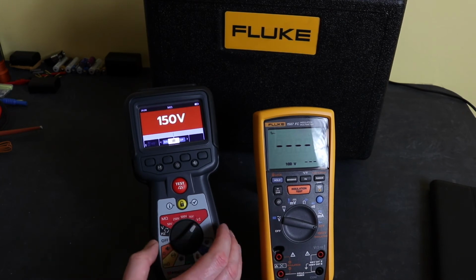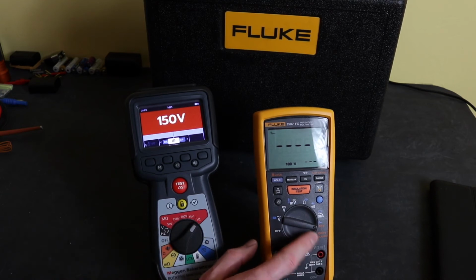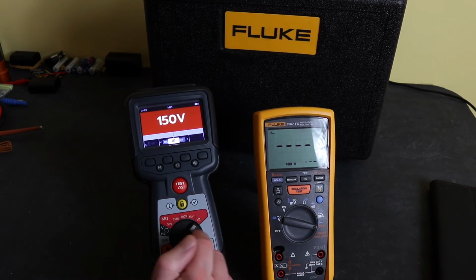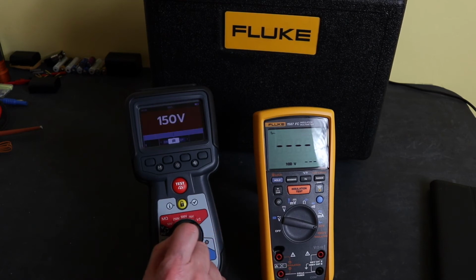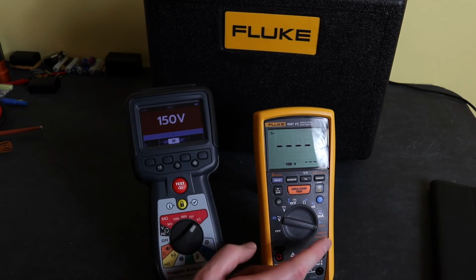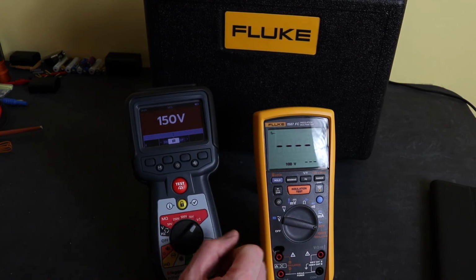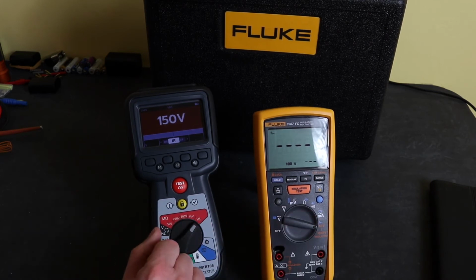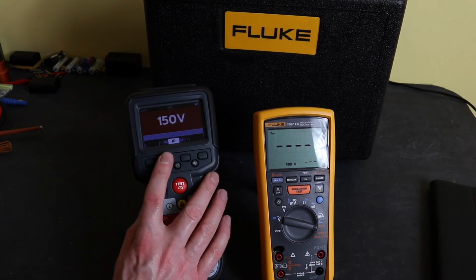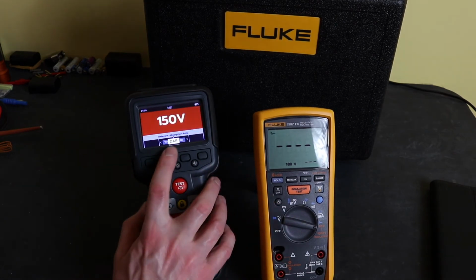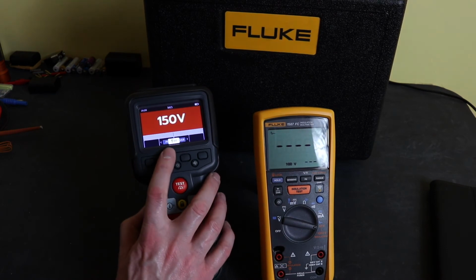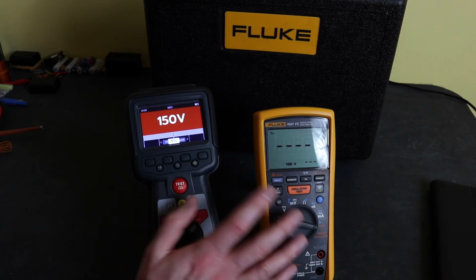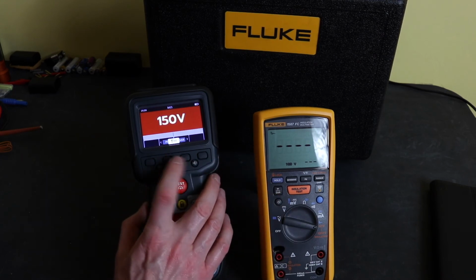To be honest, testing at these kind of levels, 1000 volts, I've never needed an averaging or a smoothing function. When I'm testing at 5kV and 10kV, large stator windings on generators, there are times when a smoothing or average function might have been useful, but I've never used it on this kind of instrument. This also has the standard IR and also DAR and PI as well, along with standard timing function in there, so both instruments operate the same in that respect.